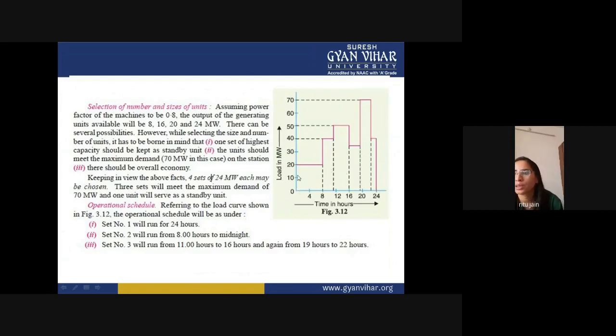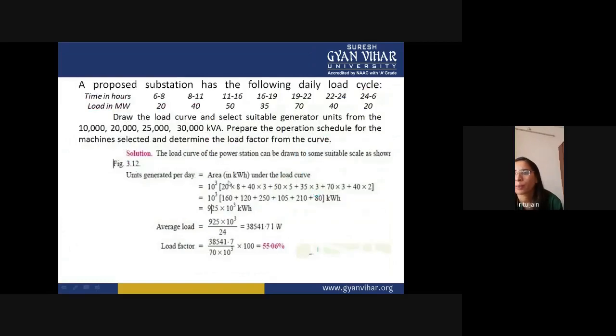So you can easily calculate the area of this rectangle. So 20 into 8. Next 40 megawatt is required for 3 hours. Like this 50 required for 5 hours. Then 35 megawatt required for 3 hours. 70 is required for 3 hours. 40 megawatt is again required for 2 hours. So you can easily calculate the unit generated per day. So it is 925 into 10 to the power 3 kilowatt hour. This much energy is generated through this power plant in a day.